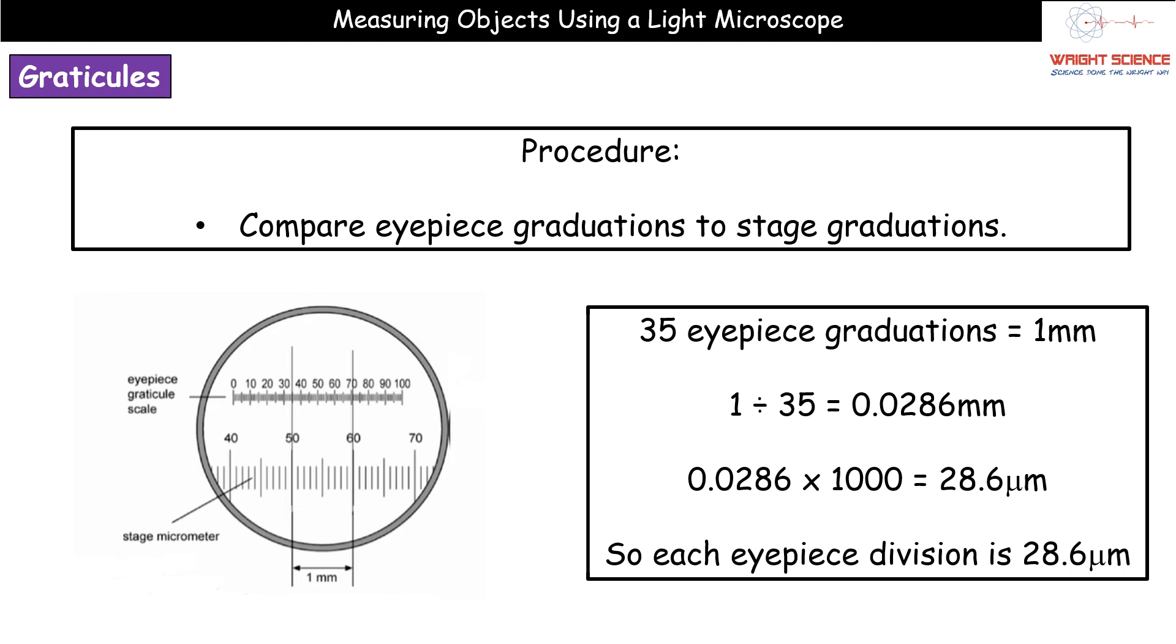What we then do is we need to compare those eyepiece graduations to the graduations on our stage micrometer. If we have a look at my little picture in the bottom left here we can see our eyepiece graticule scale is the one at the top. Here's our stage micrometer at the bottom. We've lined it up and you can see we've used the line for the 50 and we've literally brought that up onto our eyepiece graticule. Then we're going to go from 50 to 60, we're going to use our one millimeter for simplicity. Between our 50 and our 60 is one millimeter of real distance. If we count each of these little markers, we've got 35 is our starting point, 70 is the end point. So 35 from 70 gives us 35 eyepiece graduations in our one millimeter.